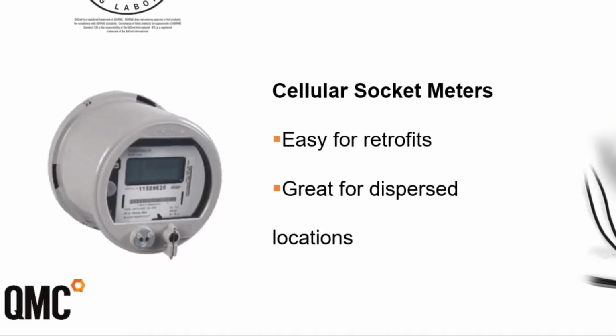The meter below it, I just wanted to showcase that metering is evolving very quickly, in that these old socket meters that you typically wouldn't think much of, a lot of the newer ones actually have cellular connectivity built right into them. So if you have 4 or 5 meter points in a property, and you see the old glass meters that somebody has to manually go and read once a month or once every 6 months, we can pull those out and put in a digital socket meter, and immediately it communicates to a cloud-based solution for $2 or $3 a month of cellular fee. It's an incredibly cost-effective way of getting automated data.